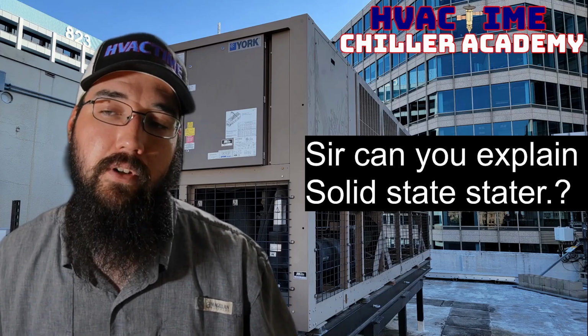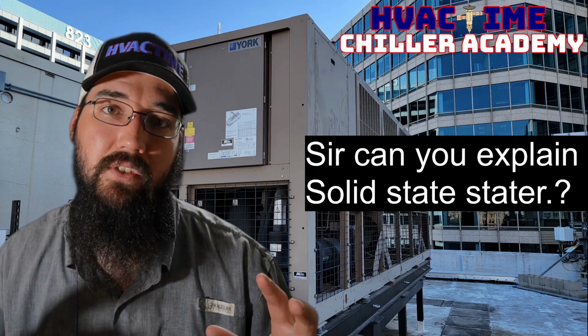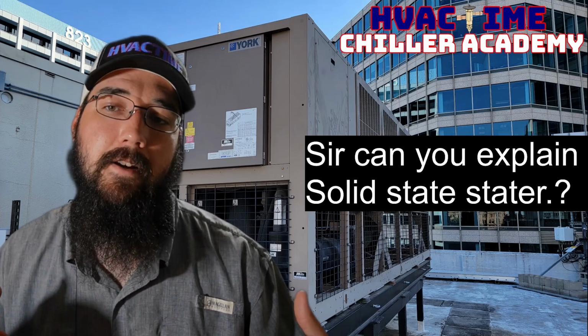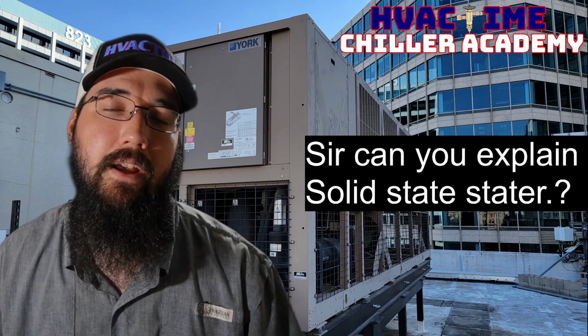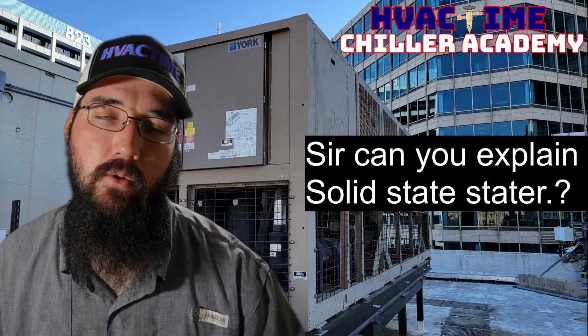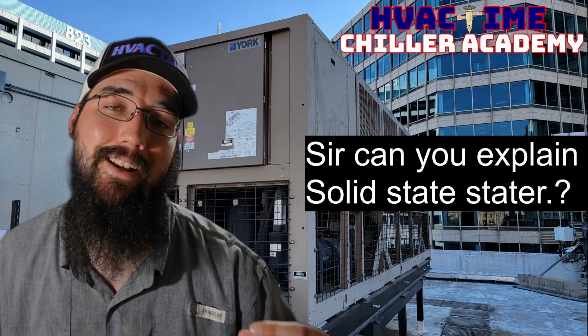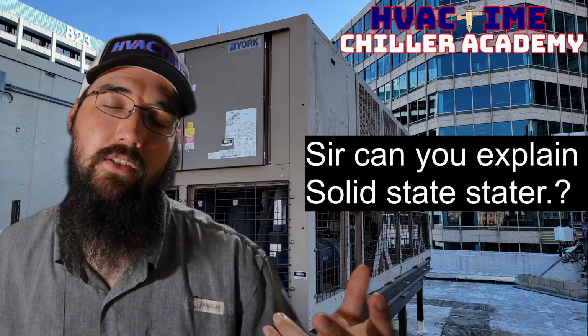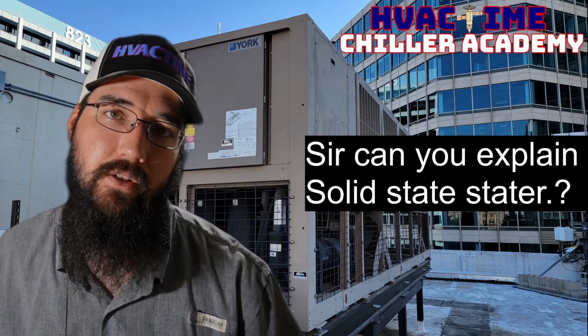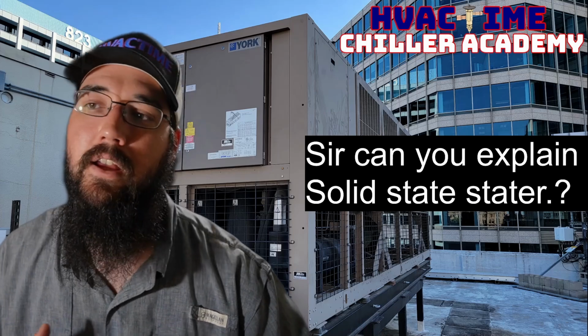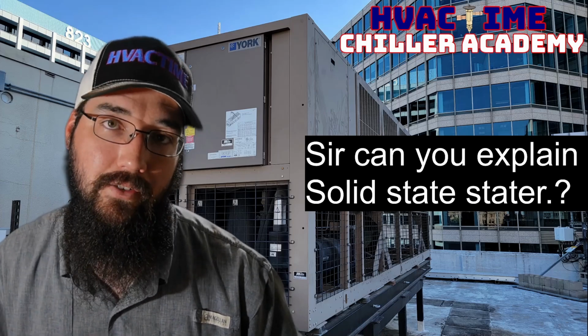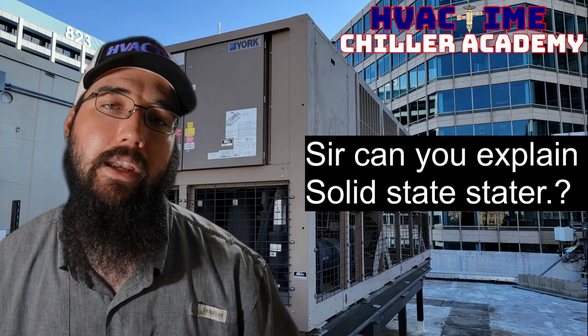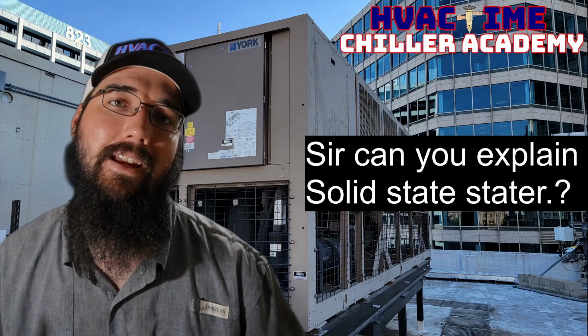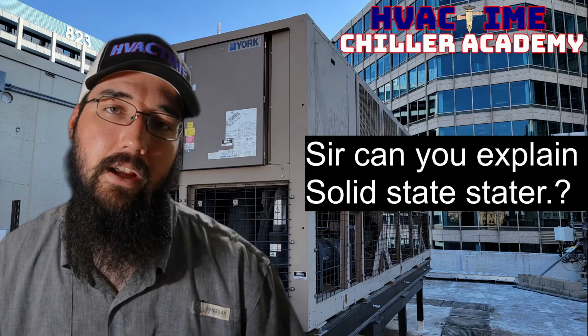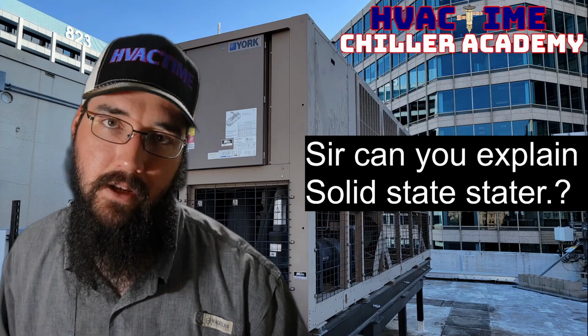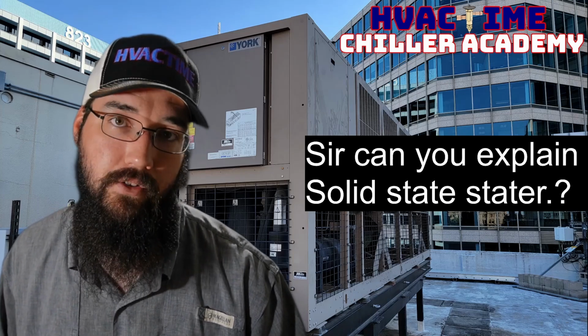There are a lot of solid state starting systems still out there that are still using bypass contacts. That's what the mechanical contact would be considered, a bypass contact. It is there for after the SCR has gotten the motor up to speed, we transition to the bypass contacts, which will then just carry the line current from there, and we can bring the SCRs out of the circuit. And by doing that, we don't need the cooling system that we need if the SCRs were to stay in the circuit. And so that is one justification for having a bypass contact involved in the first place.